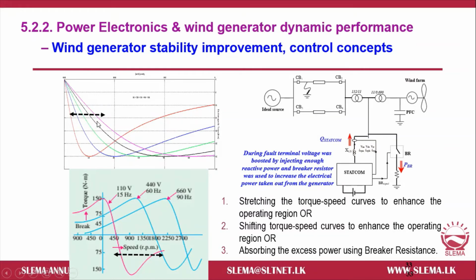That's one way of improving stability using power electronic circuits. The second way is with class 3 or class 4 generation, using DFIG or full range converters. We can completely shift the torque-slip curve from one position to another, allowing an enhanced operating region, much better than the other methods.